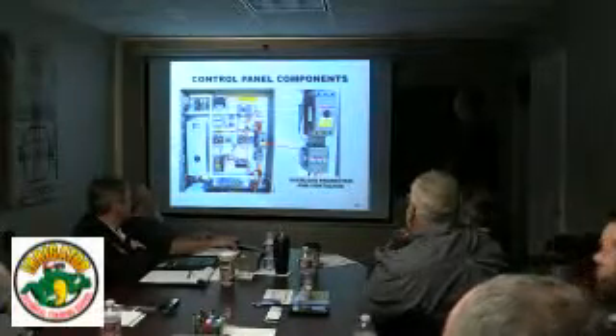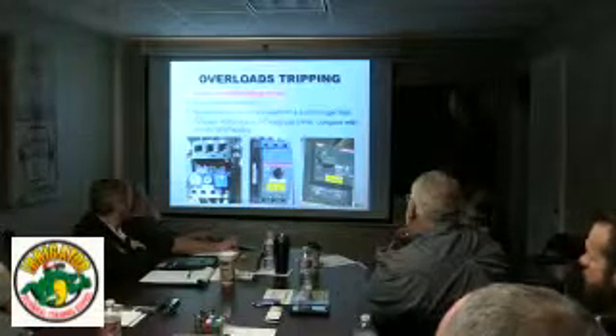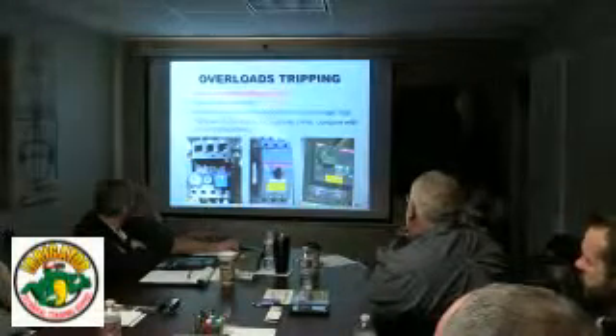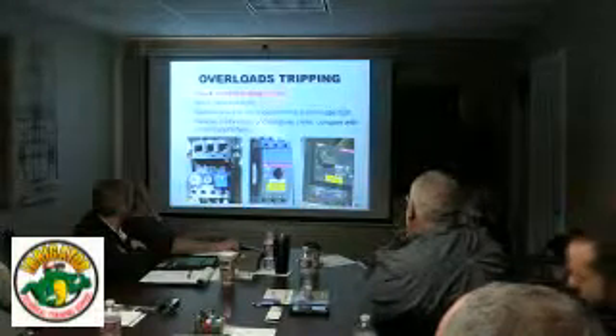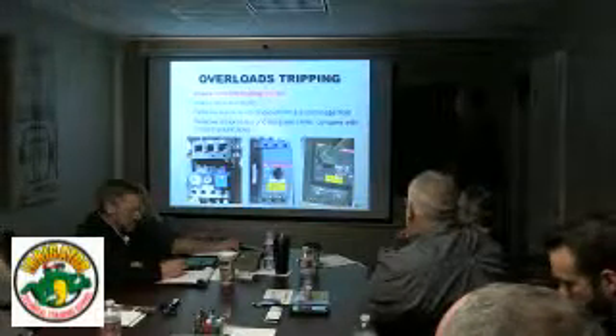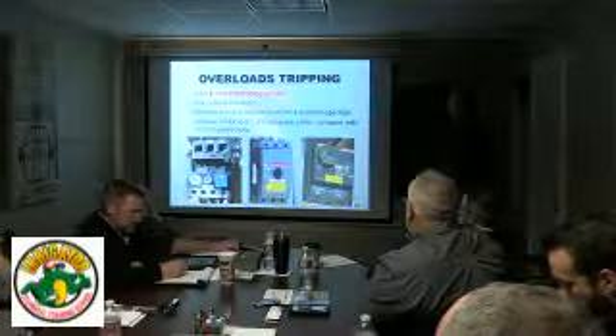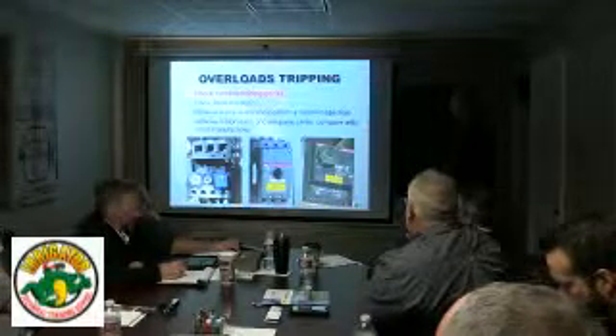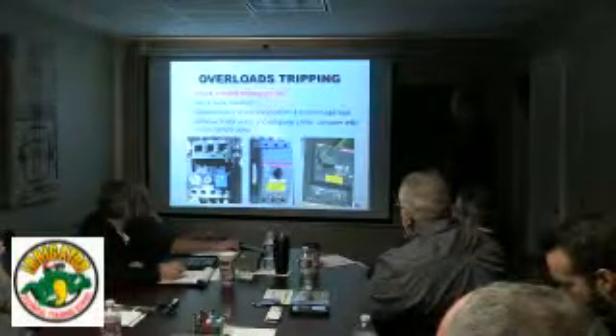Okay, now we'll look at some of these overloads and why they might be tripping, and some of the different overloads. Here are 3 overloads. We still have quite a few of these out there and we still use them once in a while. This is simply an overload for a contactor. There's a little indicator over here that says it's tripped.